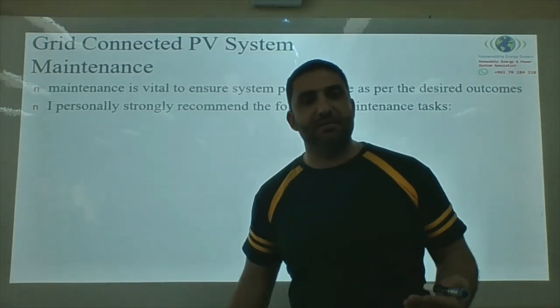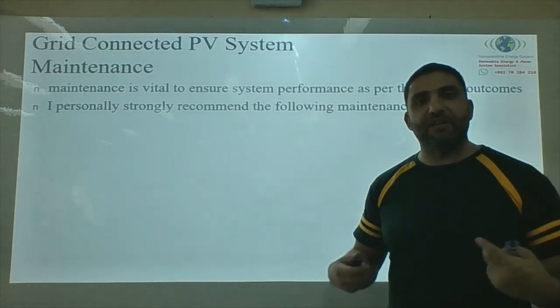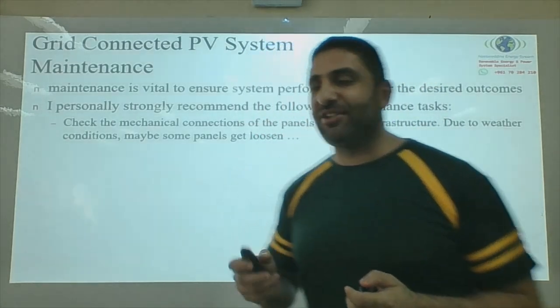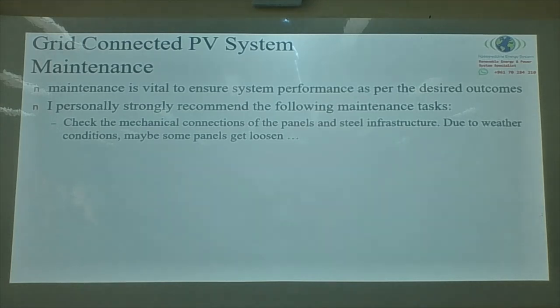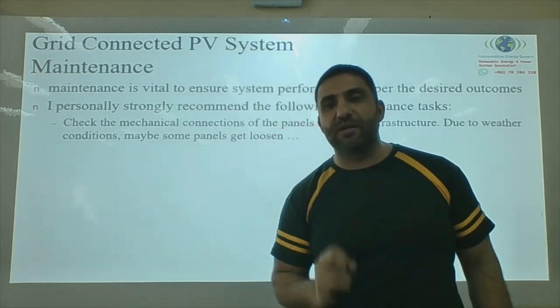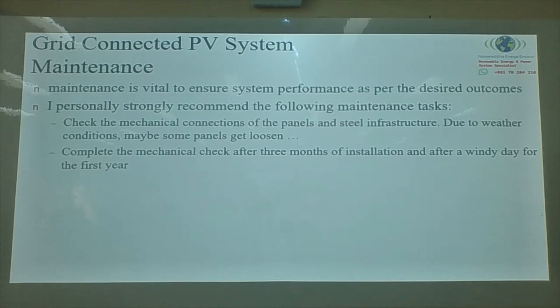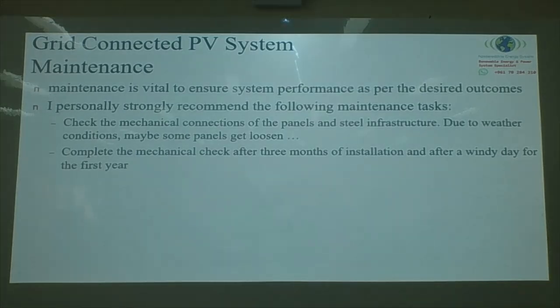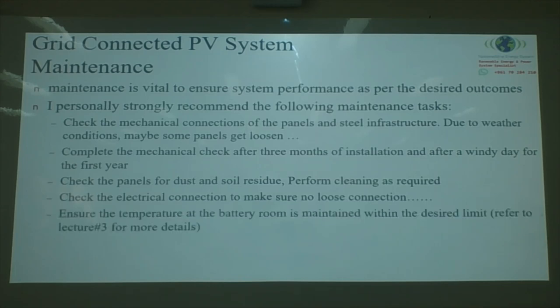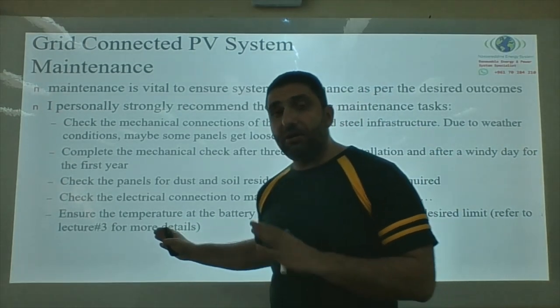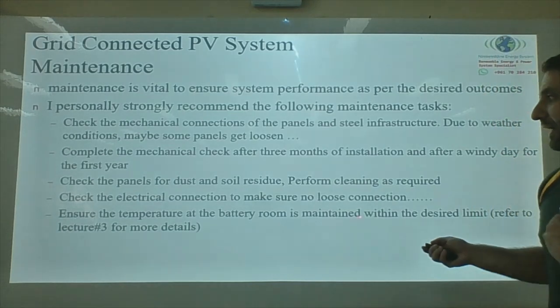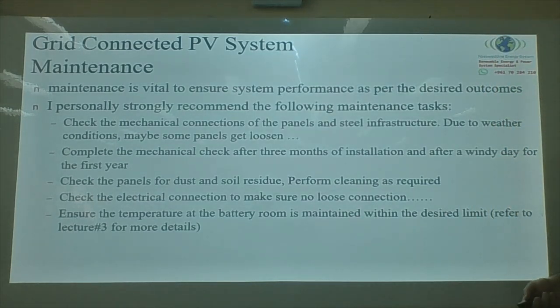Solar systems require very minimal maintenance apart from cleaning. Strongly recommended checks include: mechanical connections to the panels (loose screws after wind); perform a mechanical check after three months of installation or after a windy day in the first year; check panels for dust and soil residue and clean as required; check all electrical connections for looseness; and ensure battery temperatures stay within acceptable limits to avoid damage.